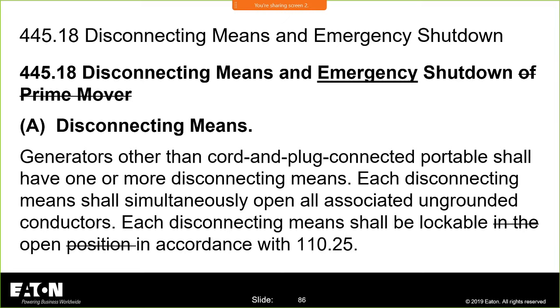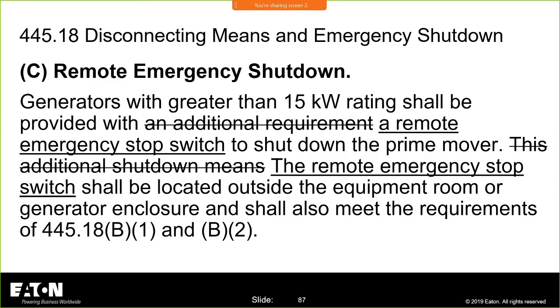So in A, disconnecting means, we basically said, each disconnecting means shall be lockable open in accordance with 110.25. You'll notice it doesn't say only lockable open. It just says lockable open. If my switch is lockable closed, I would not be violating 445. And then in C, they made a change. They said that generators with a greater than 15 kilowatt rating shall be provided with a remote emergency stop switch to shut down the prime mover. The remote emergency stop switch shall be located outside the equipment room or generator enclosure and shall also meet the requirements of B1 and B2. And to refresh your memory, B1 and B2 says it has to be equipped with provisions to disable all prime mover start control circuits, and it requires a mechanical reset.